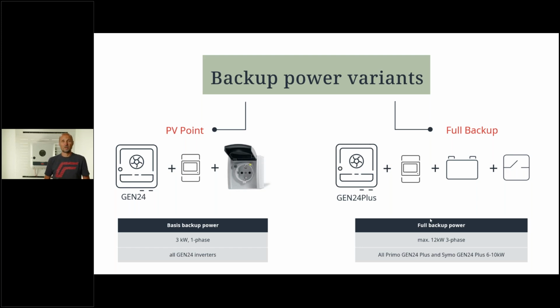Or the other solution, the full backup solution. Here we need to have a Gen 24 Plus inverter. It can be a Primo or a Symo. If it's a Symo, we need power class from 6 to 10 or 12 kilowatt in the new inverters. We have a maximum 12 kilowatt three-phase AC output, with which we can supply all the backup power loads. Therefore, you also need a battery. A battery is always required, and a smart meter from us, of course, and the switchover component. I will show you in the next slide what you need exactly for that.